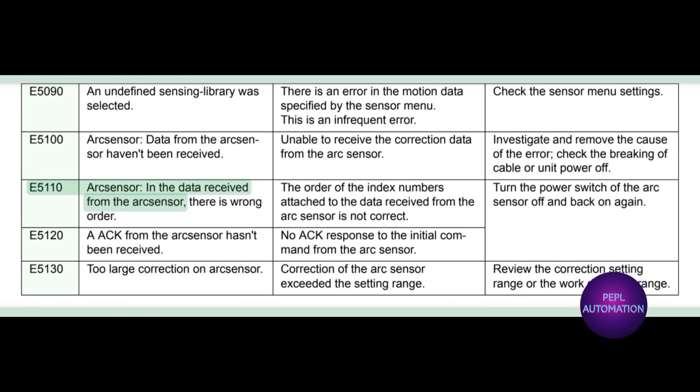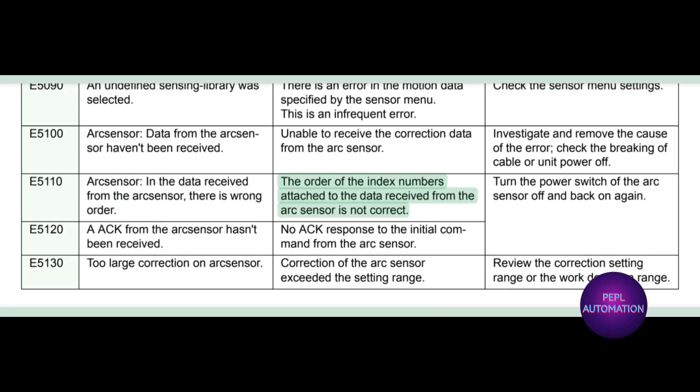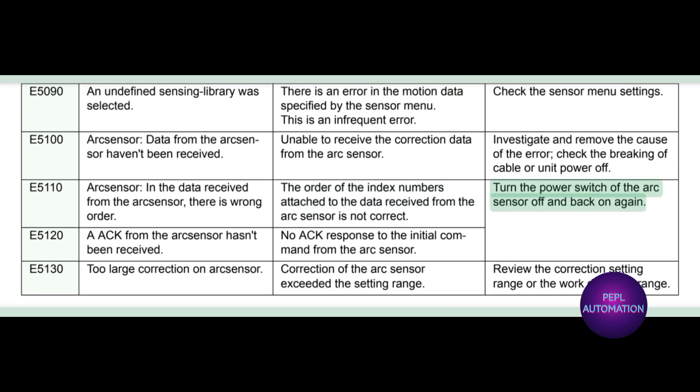E5110 arc sensor: in the data received from the arc sensor, there is wrong order. The order of the index numbers attached to the data received from the arc sensor is not correct. Turn the power switch of the arc sensor off and back on again.